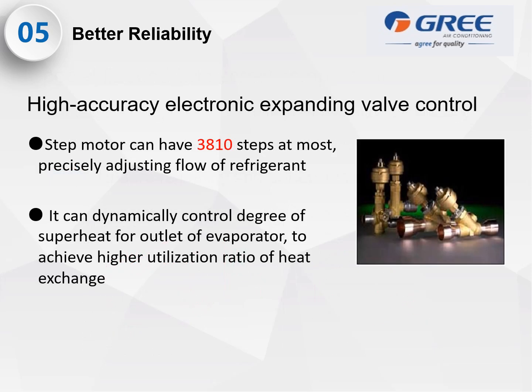High accuracy electronic expansion valve control. It has a step motor up to 3,800 steps, the most, precisely adjusting refrigerant flow. It can dynamically control degree of superheat for outlet of evaporator to achieve higher utilization ratio for heat exchange.